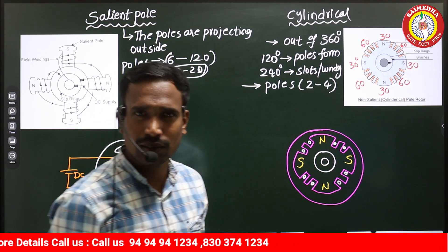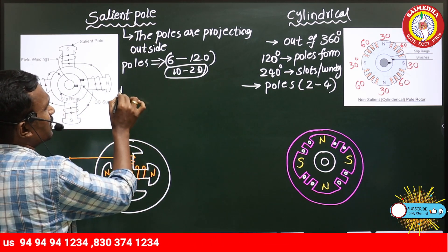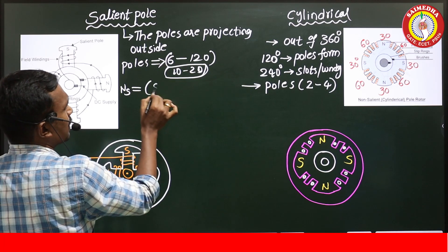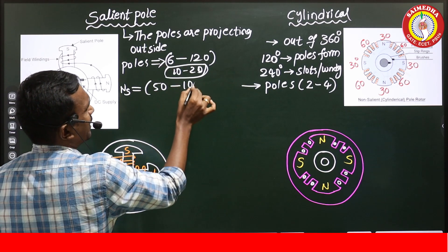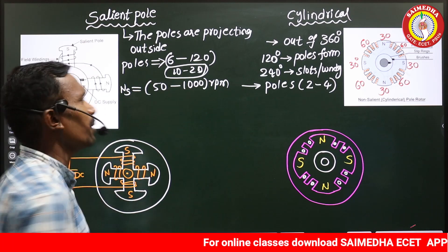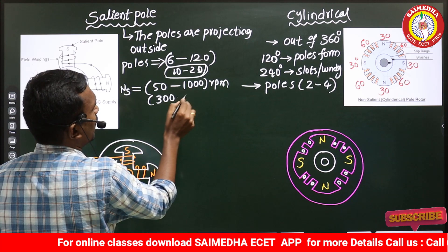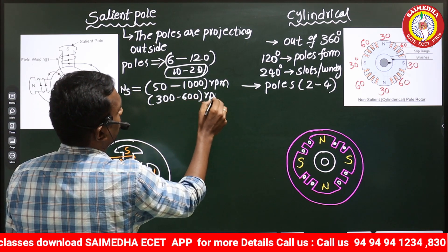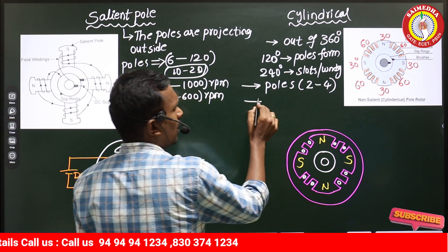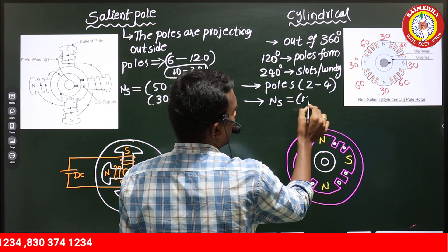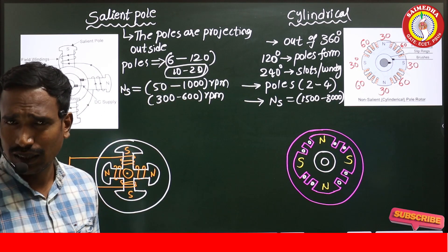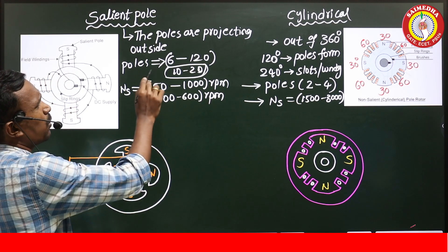For a 50 Hz supply, with 120 poles the speed is 50 RPM, and with 6 poles the speed is 1000 RPM, so the speed range of the salient pole machine is 50 to 1000 RPM, practically 300 to 600 RPM (300 RPM for 20 poles, 600 RPM for 10 poles). For the cylindrical type, the synchronous speed range is 1500 to 3000 RPM for a 50 Hz supply.